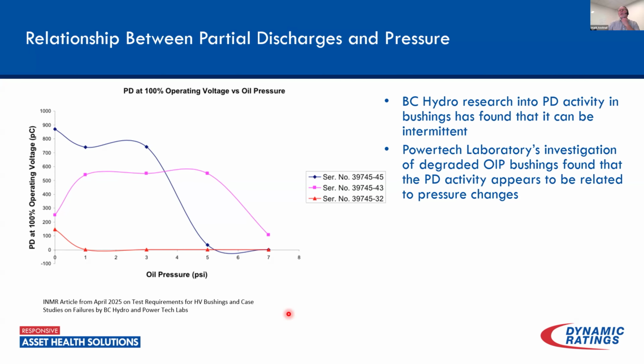So this was some research that was done by BC Hydro. They had some degraded bushings that they put in the lab, and they increased the pressure within that bushing. They wanted to see how the partial discharge behaved. What we're seeing is when the pressure is high, basically at elevated loads, the picocoulombs of that discharge are actually relatively small. But if they go back to 0 psi, we can see much higher picocoulomb values. So again, the higher the picocoulomb, the greater the discharge, and that could degrade our insulation.